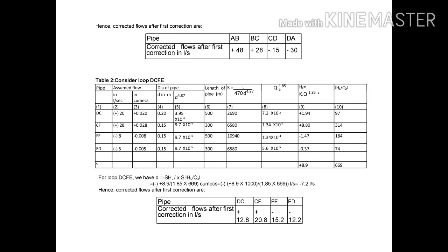Then go to the other loop, consider loop DCFE. Going through the diagram, the corresponding flow, diameter and length are all substituted here, and simplifying gives the HL value and the HL by QA value. Once again for loop CDEF, you find the correction delta Q value, and you get minus 7.2 liters per second. After applying the correction to the corresponding pipelines, you get the corrected flows after the first correction in liters per second.